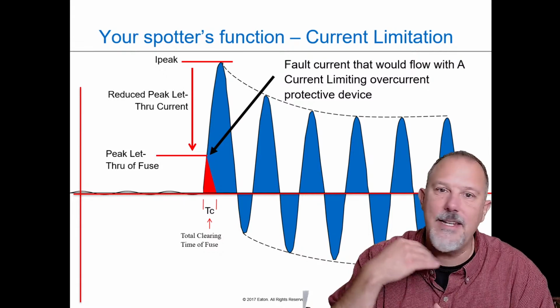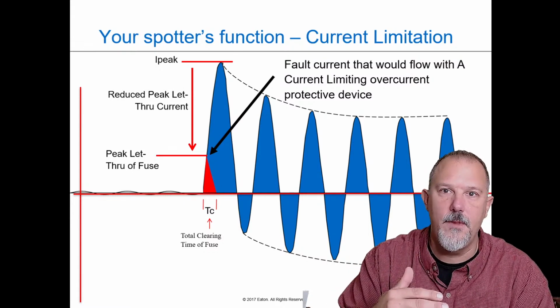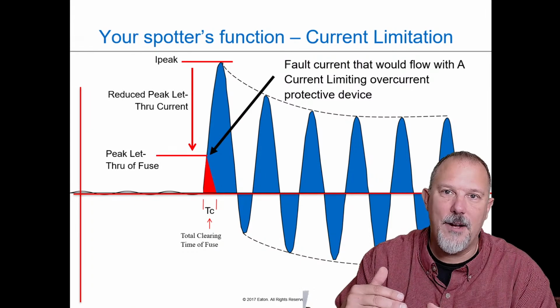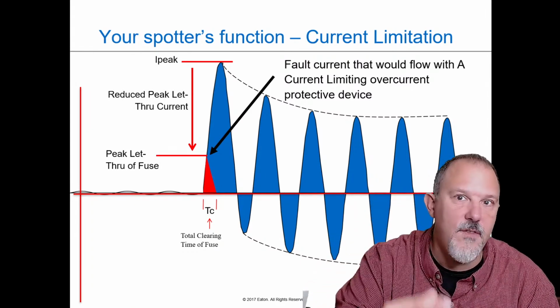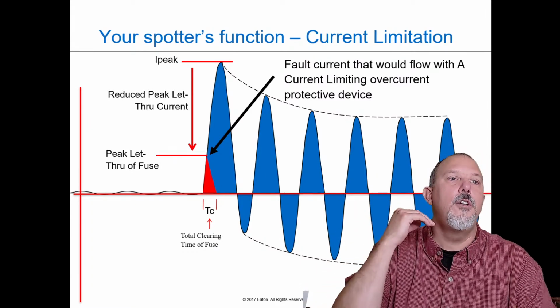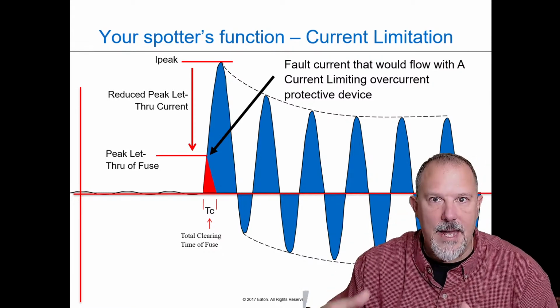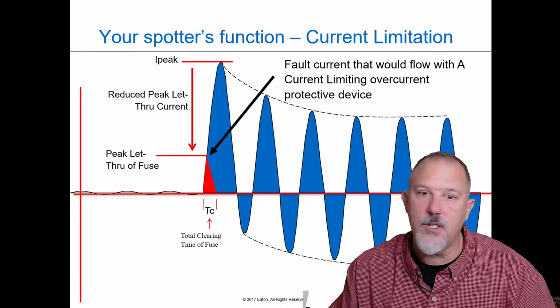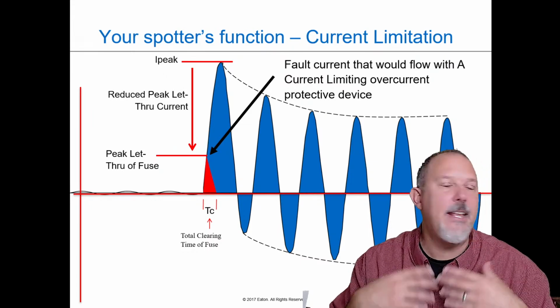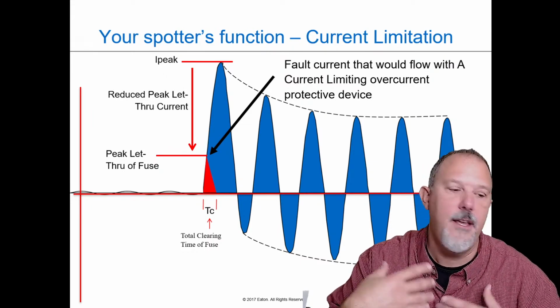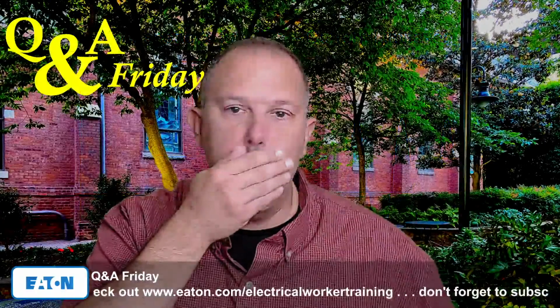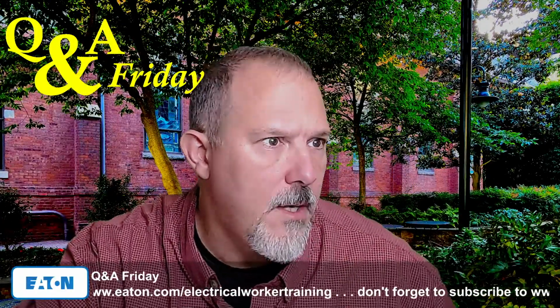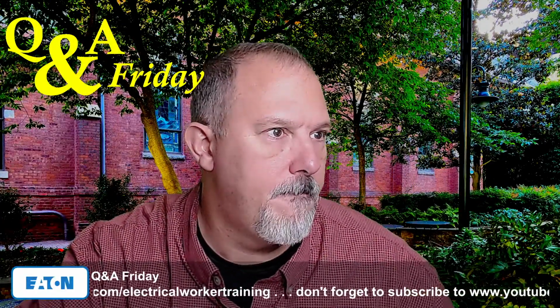And if it did not see 10,000 amps RMS, right? It didn't see the peak current that you would have seen if you had a fault that was 10,000 or greater than 10,000 amps. It saw something much less. And the translation is in protecting the equipment. So that's basically what you got going on there.